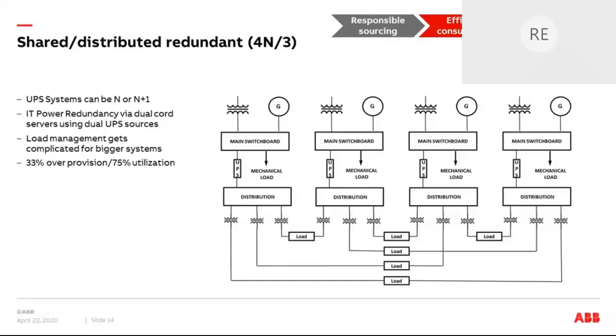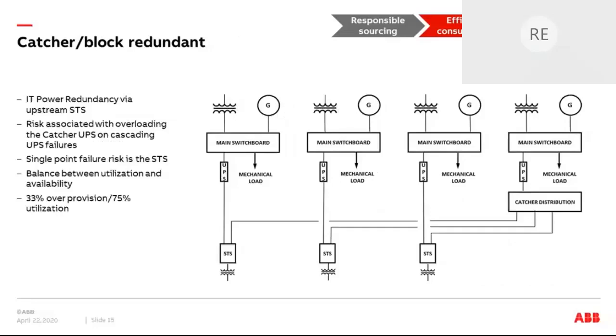More recently, some clients have gone to block redundant or catcher systems. The top looks similar to the previous, but now on the far side we have a catcher distribution board, and we're switching between IT loads through an STS, so we've added 3 STSs at the bottom. STS is a static transfer switch, allowing you to switch between loads very quickly, and this gives you single-corded topology on the IT side, which saves a lot of copper.